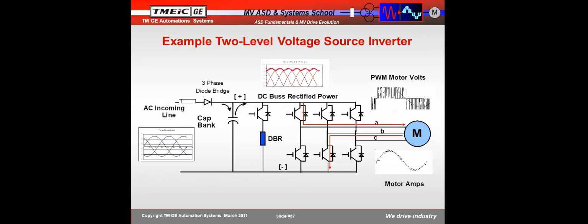Now let's look at our output levels. I think this is very, very important. What you're looking at is a low voltage drive. And basically, if we turn on that top IGBT, it gives us positive voltage. If we turn on the bottom one, it gives negative voltage. That's an oversimplification, but it's good enough for our use today. And so you look at this waveform up here, and you've got your 0 voltage, then your high voltage, which on a 480 volt drive might be 650 volts.